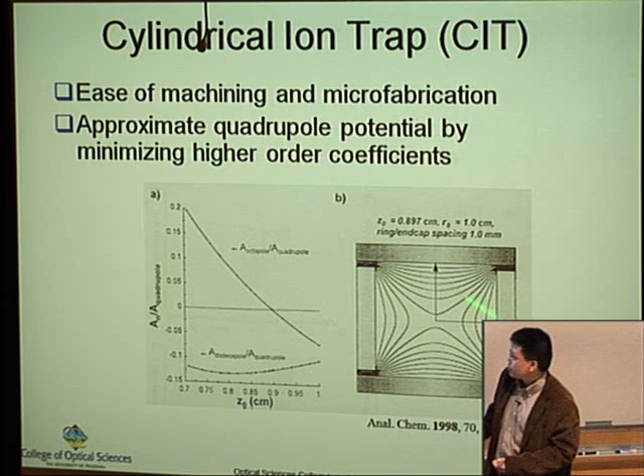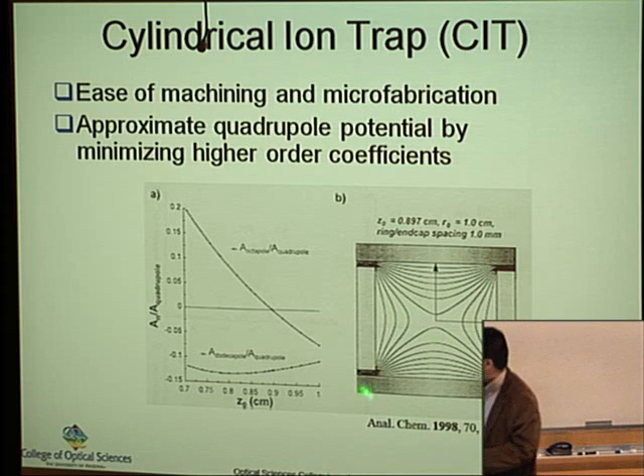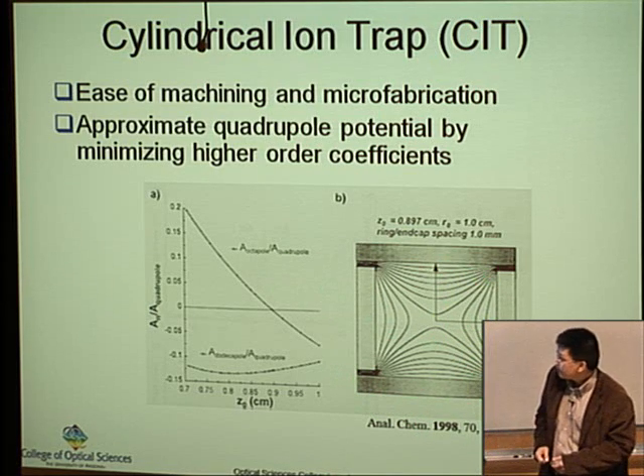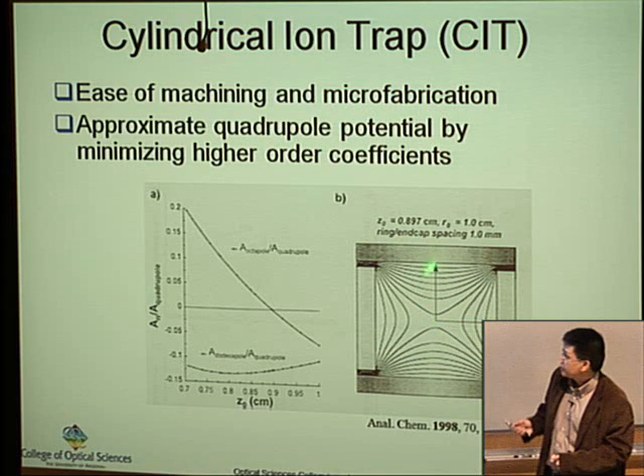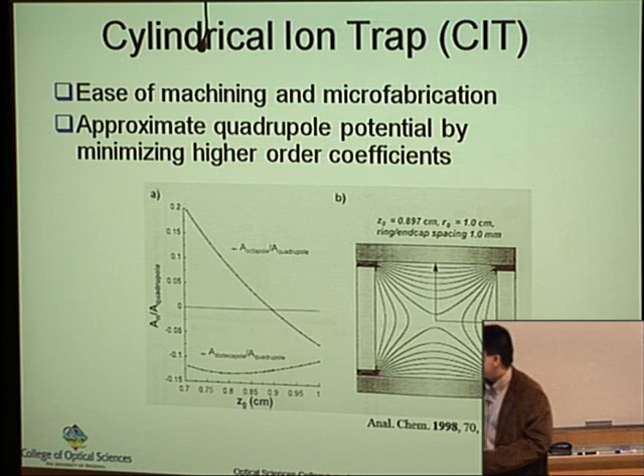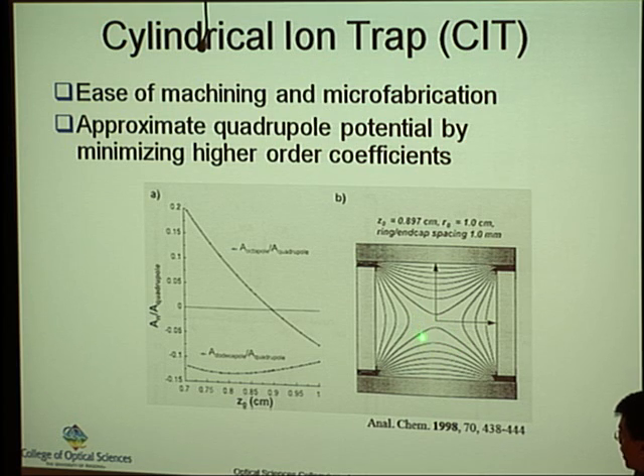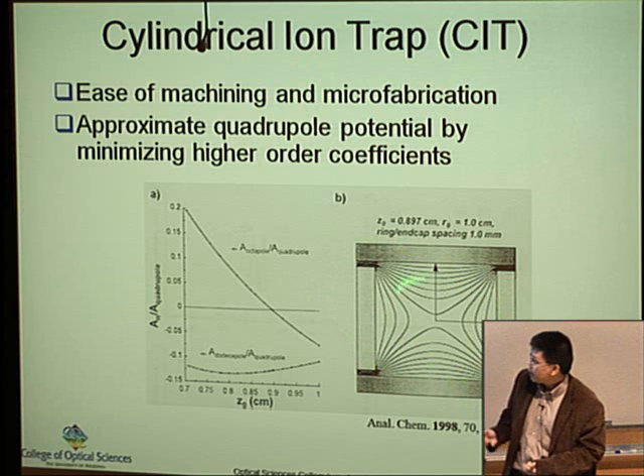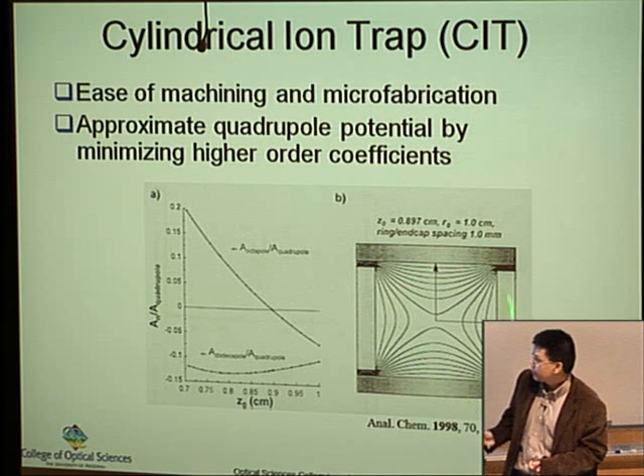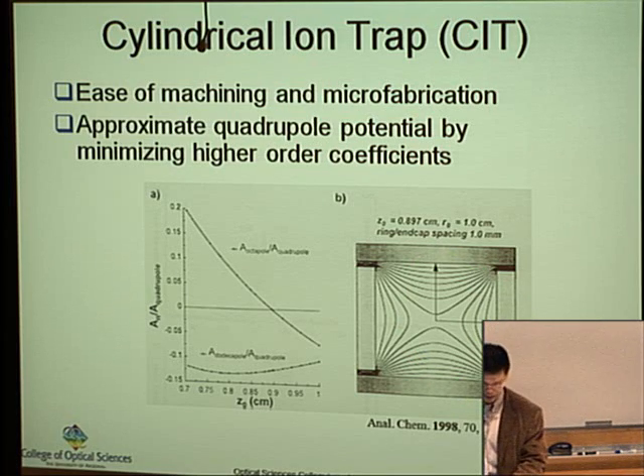It turns out that if you use a cylindrical electrode — consisting of a bottom ring, a middle ring, and a top ring — and define the dimensions such that the ratio of the Z dimension to the radius is about 0.897 to 1, then through simulation you can show that the octupole potential component is zero and the dodecapole potential is minimized, maximizing the quadrupole potential. This cylindrical structure is much easier to fabricate than hyperbolic electrodes.